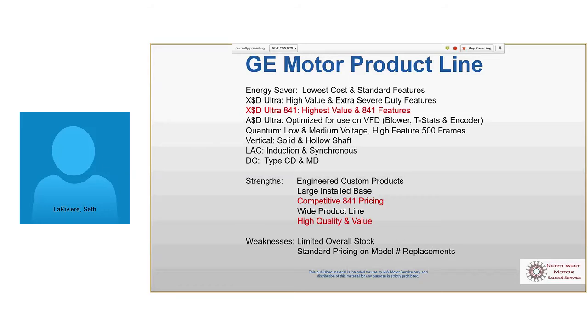So what they do on these that are optimized, they have an external blower motor that always runs at 1800 RPM, independent from the main motor, blowing constant velocity air over the motor. So it cools, and they can run at really slow speeds. And I'm not kidding, literally zero speed, full torque at zero speed.